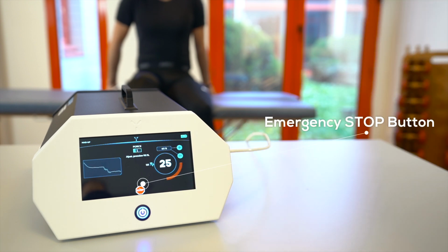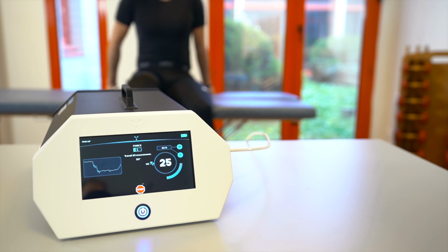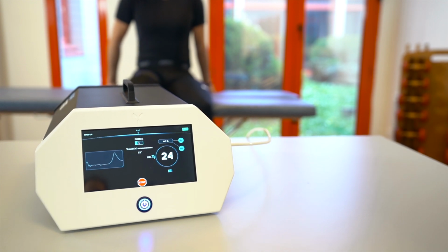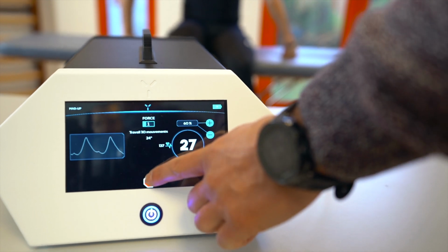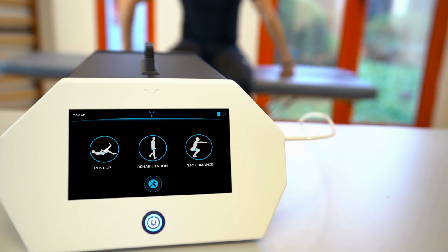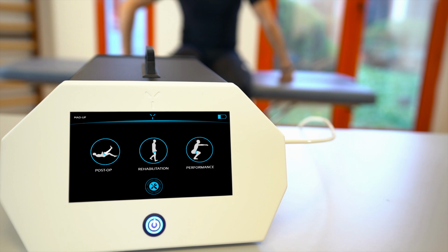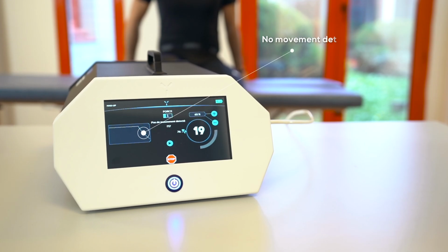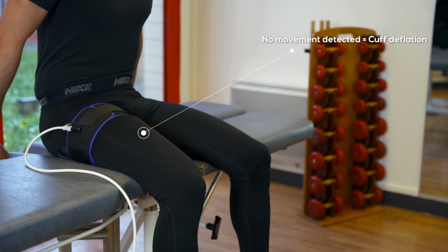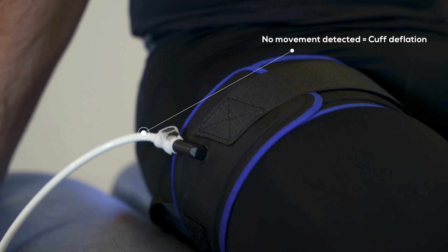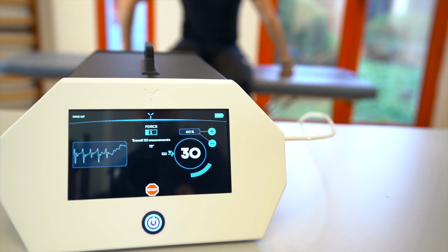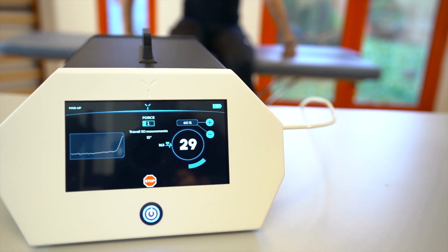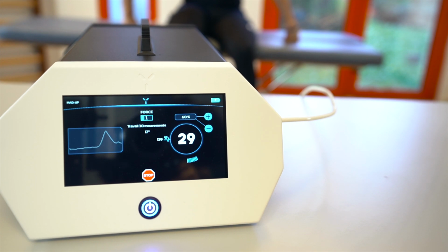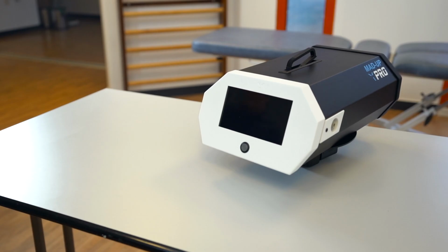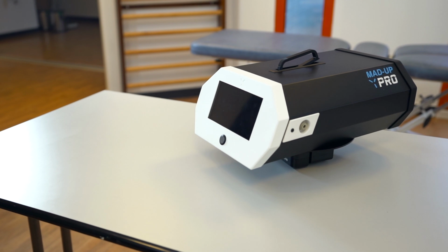If necessary, an emergency stop button is accessible at all times. Pressing this button will immediately depressurize the device. If no movement is detected for several seconds, the device enters safety mode and automatically deflates the cuffs. Once the protocol is finished, the device will start the next protocol after a 1-minute pause. The device will gradually depressurize the cuffs before displaying a statistical summary of the completed session.